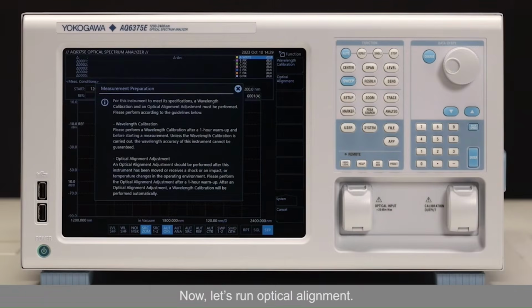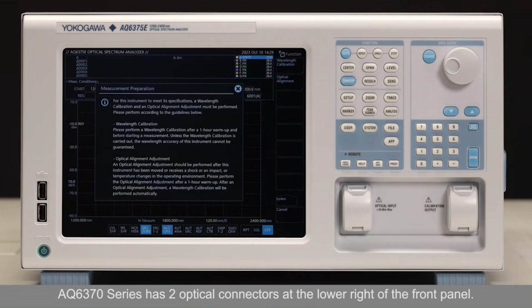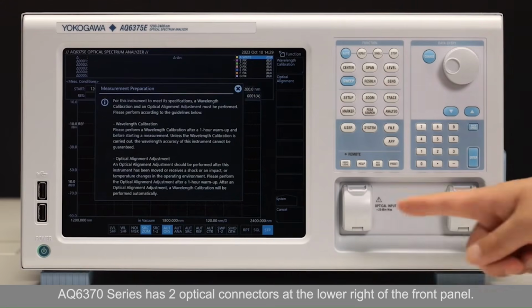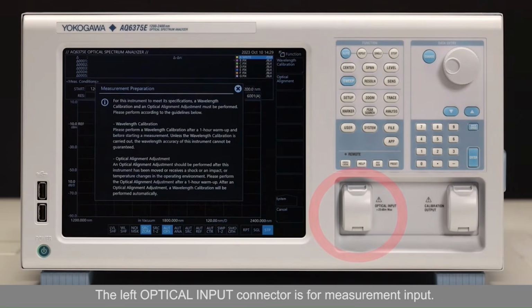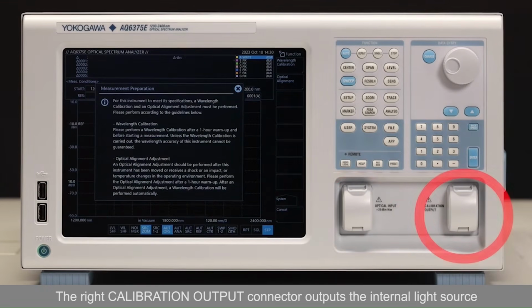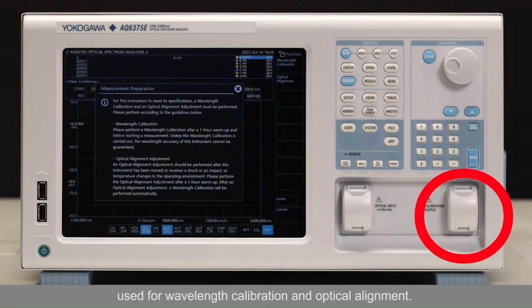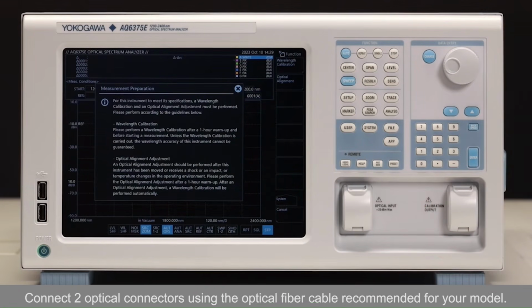Now let's run the optical alignment. The AQ6370 series has 2 optical connectors at the lower right of the front panel. The left optical input connector is for measurement input. The right calibration output connector outputs the internal light source used for wavelength calibration and optical alignment. Connect 2 optical connectors using the optical fiber cable recommended for your model.